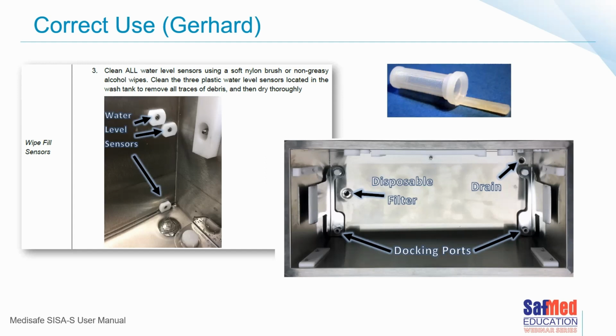On the right-hand side top is a picture of the disposable filter that is in the machine that will prevent debris going through your different pumps. And that should be changed minimum on a daily basis. If you look inside on the bottom right, the inside of the chamber, you've got the docking ports, you've got the drain in the one corner, and you've got your disposable filter on the other side. It is important to clean these sensors and to replace the filters as described in the manual for different makes of machines.